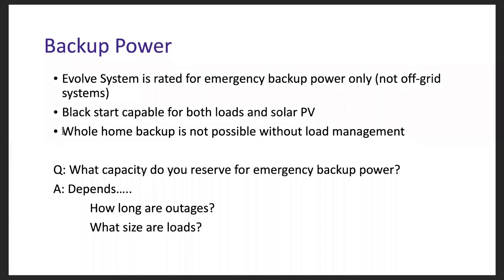So some design considerations that differentiate our product from others. Really what we try to promote is management of expectations. And when your customers experience a grid outage and for some reason the battery is tripping offline because there are too many loads on it, you instantly become the utility, answering phone calls and having to go back to explain to customers why a battery is tripped offline. That is really problematic and probably outside of your best business case.